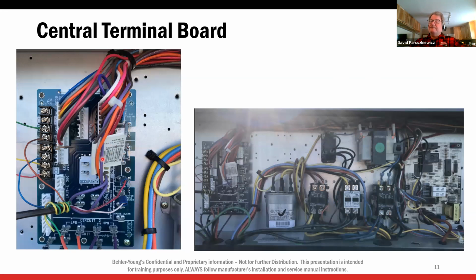All right, so the central terminal board, we're going to take a look at first, as you see here on the left. And again, if you take a close look at this board, there's no logic on there at all. It's a terminal strip. This is a junction point. You can see right here, this is where your thermostat terminals are. Down here, you can see your pressure switches, low pressure, high pressure, low pressure, high pressure, which is a great place to check the switches to see if they're open or closed. Then over here is your smoke detector inputs. All right, so it's a pretty straightforward, simple little device.